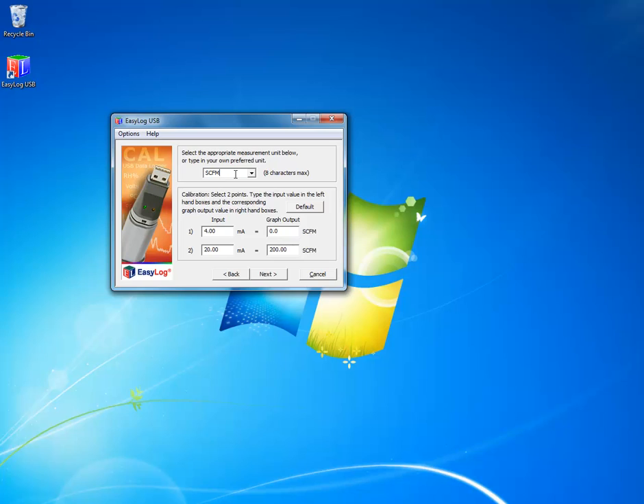4 mA equals 0 SCFM. 20 mA equals 200 SCFM. So put in your value into the bottom right corner here. This is where your max output value will go. And then click next.